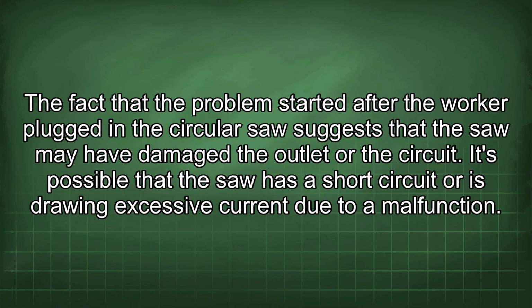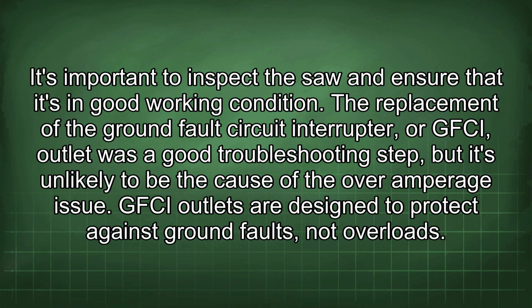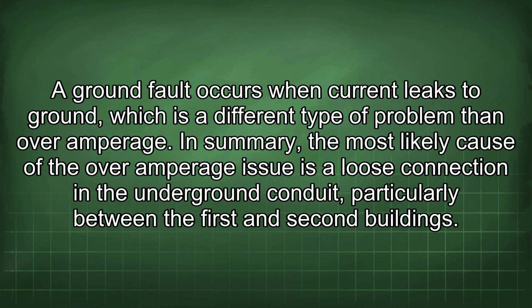The fact that the problem started after the worker plugged in the circular saw suggests that the saw may have damaged the outlet or the circuit. It's possible that the saw has a short circuit or is drawing excessive current due to a malfunction. It's important to inspect the saw and ensure that it's in good working condition. The replacement of the ground fault circuit interrupter, or GFCI, outlet was a good troubleshooting step, but it's unlikely to be the cause of the over-amperage issue. GFCI outlets are designed to protect against ground faults, not overloads. A ground fault occurs when current leaks to ground, which is a different type of problem than over-amperage.